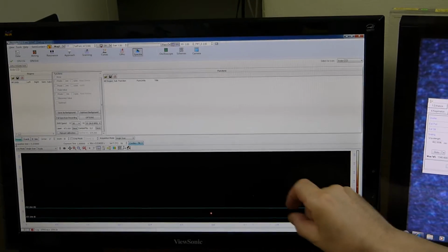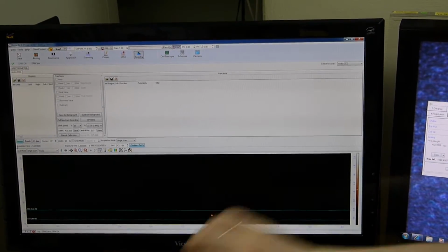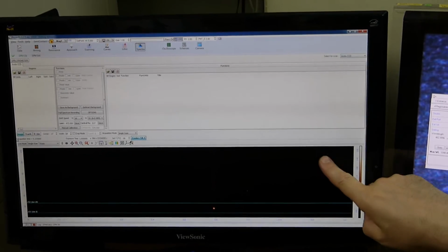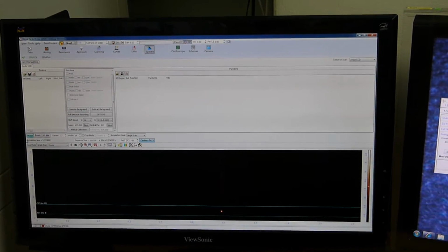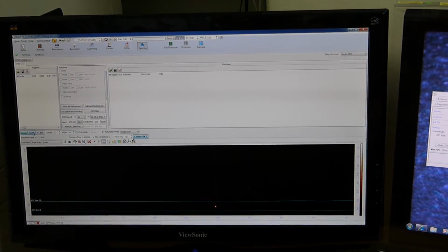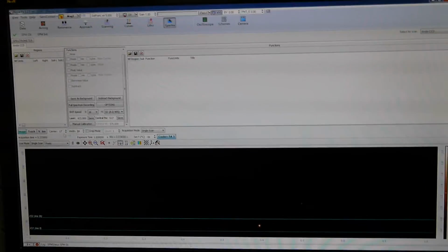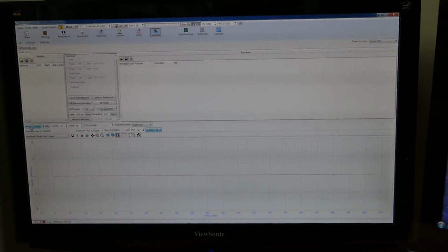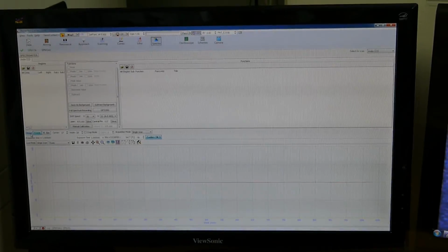The track is only here. If you select full binning, the whole matrix will be read. The signal will be a little more noisy because it will read noise. This is the reason to work in track mode. We specify this track height 17 here and width of 20. You can check one time and forget about this, but it is better to work in track mode. Every time it will be the same position, the same height. I check for all of them.